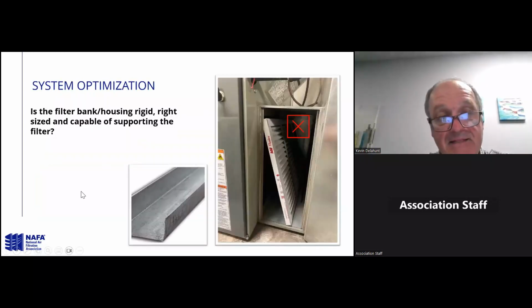And to optimize that system, as Tony said, I've been in the industry 40 years. The U channel in the left-hand side picture was there 40 years ago, and might even have been there 40 years before I started, but it hasn't really changed. When I started, you still had metal washable filters and light grade throwaway filters. And I'm going to show you another chart here where the effect on performance is not that great on a MERV 6 or less filter.